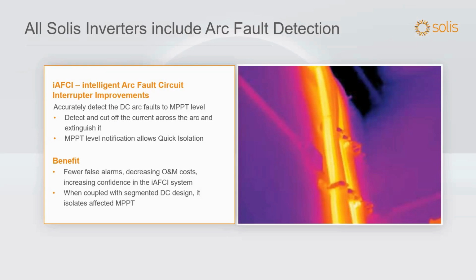We don't want these things too sensitive where they're detecting a little bit of moisture and causing you a truck roll - no, we want to make sure these are real alarms. It'll watch that alarm, and if it's strong enough, it'll send the alarm right away. But if it's not quite strong, it'll wait and only send the alarm code when it's confident this is something that needs to be serviced right away. The inverter will shut down, and the alarm will tell you what string it's on.